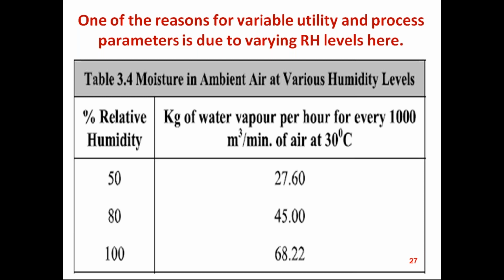As I said before, 50% RH and 100% RH, or 80% RH, you can see the RH is getting almost doubled. Between daytime and nighttime there is RH variation and temperature variation, as well as in summer and winter. All these variations will definitely affect the compressor performance. So we have to see the compressor performance based on the air intake temperature and RH only. The compressor OEMs follow IS 1217 as the standard. They give the FAD, free air delivery, for the given compressor at a reference of say 20 degrees centigrade and RH of 0. And the flow meter also has to be put in the line after the dry air receiver when it is going to the process. It cannot be installed immediately next to the compressor. That will give wrong readings because it will measure more of the moisture in the system.